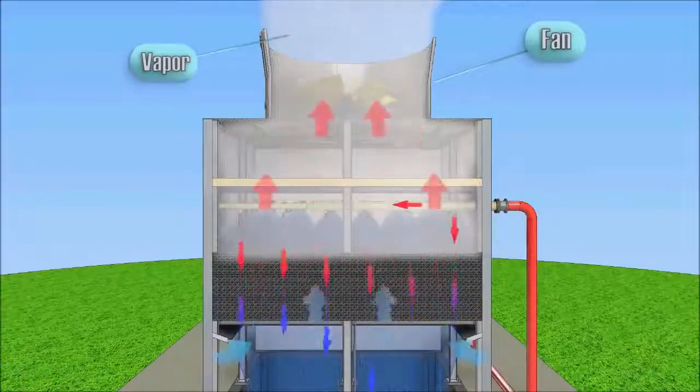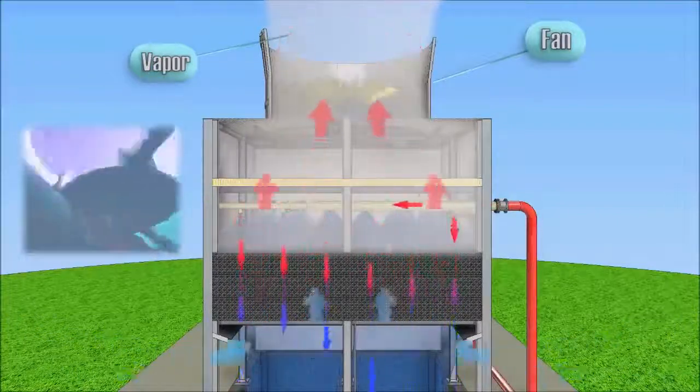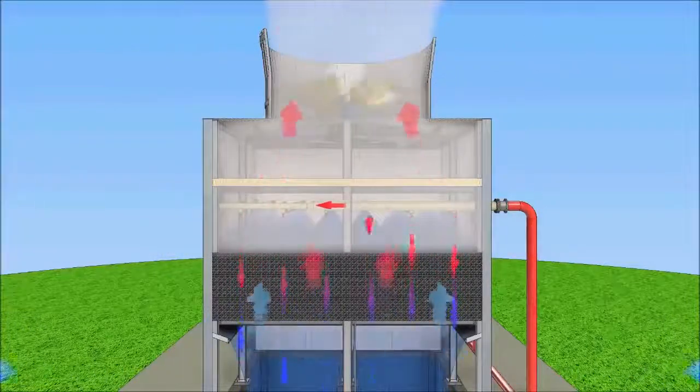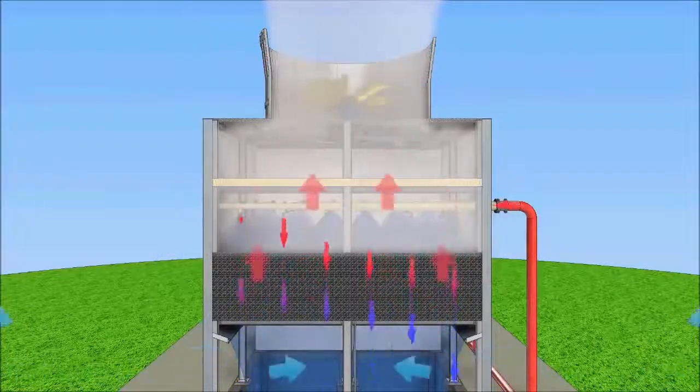The air passes through fills saturated with water vapor. The water cooling efficiency of fan cooling towers may be controlled by varying the supply air fans and changing fan speed. The limit of cooling water in the cooling tower is the temperature of the outside air wet bulb temperature.